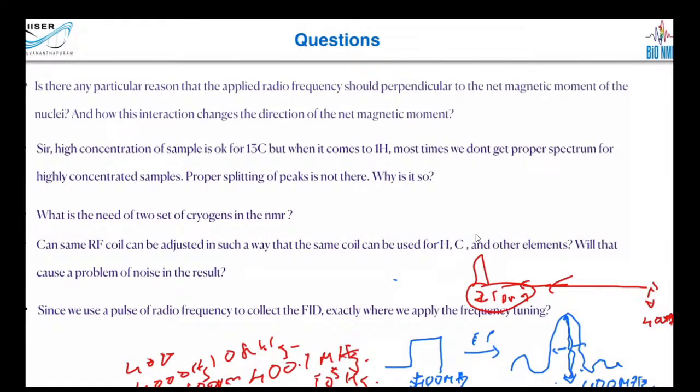But since all your spectra are in this region, 0 to 10 ppm, that is very far away from 25 ppm. You will not have a 90-degree pulse here. A 90-degree pulse will give you optimal sensitivity, or 30-degree when you're doing that. But you will not have the right sensitivity if your offset is really huge. This is the offset, right? It's 25 ppm. That is really huge. So you don't want to do that. You have to have it at exactly the right frequency.